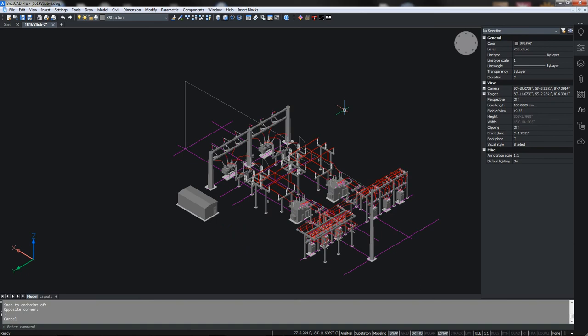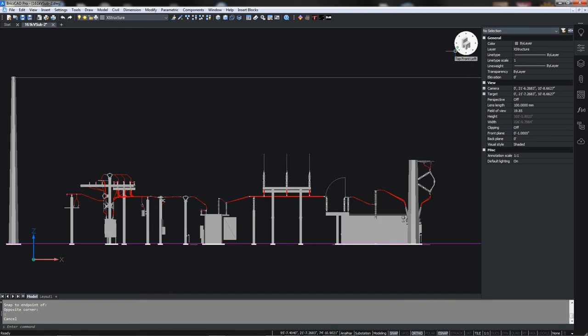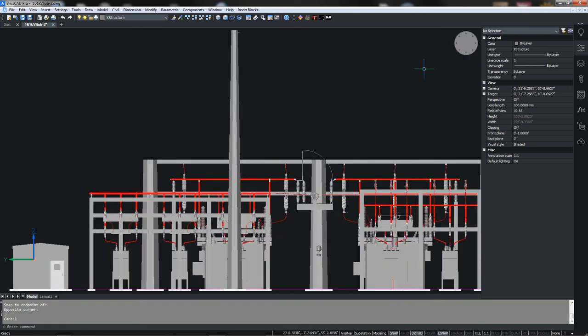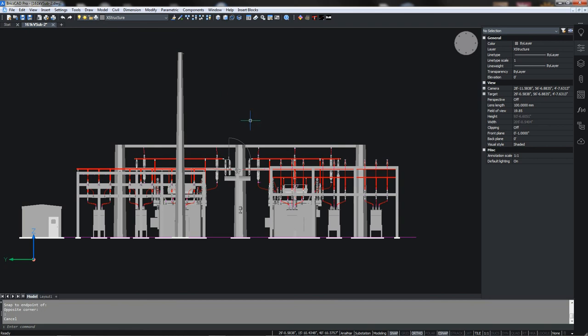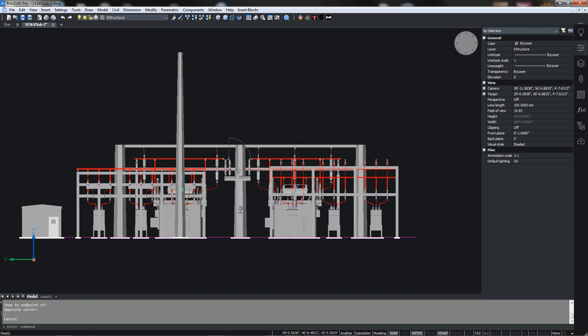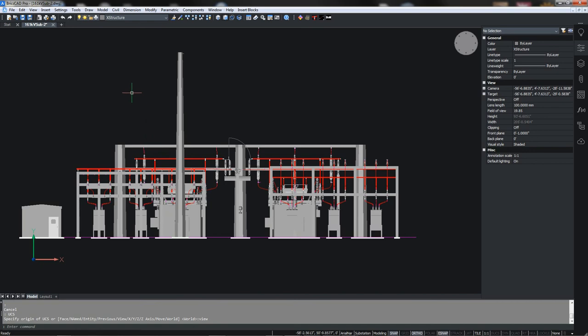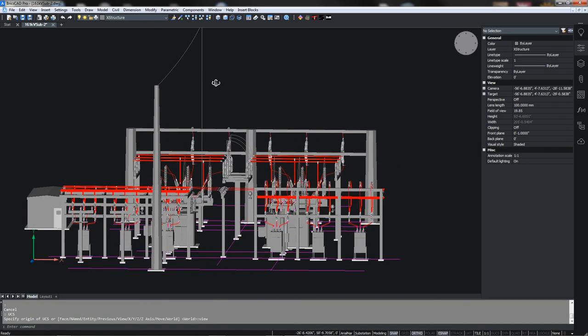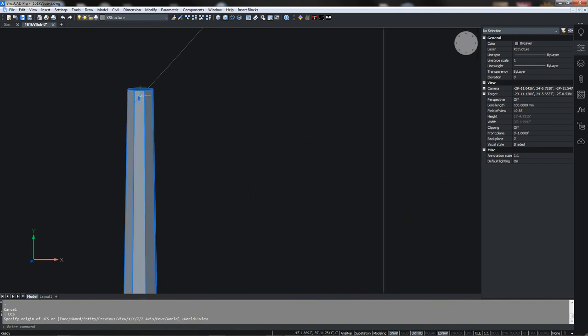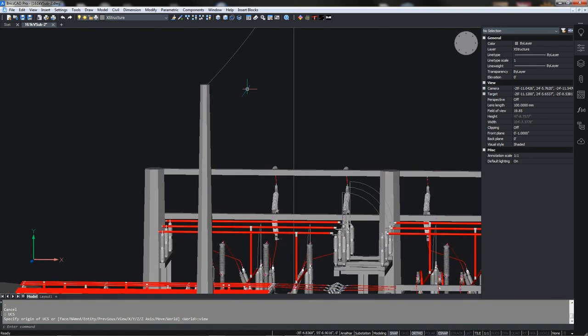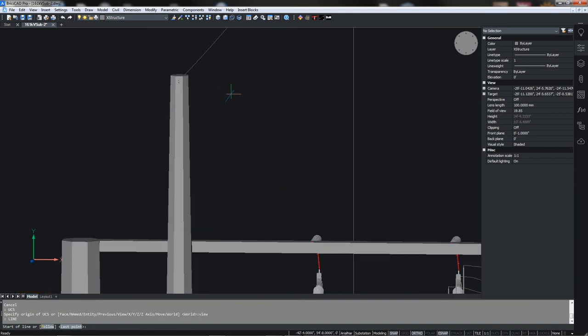Now we want to go to our fixed angle method. First thing I want to do is get the right view. We need to draw our shield lines along here, recognizing that there will be another lightning mast over here and shield wire. On this side we'll have 45 degrees, this side will be 30. In order to draw that line we really need to have our UCS in the XY plane to simplify that construction. We simply use the UCS command and we want it to just be the view that we're looking at, so we use the view option on UCS. Now we need to start with putting in our shield lines. I'm going to move this slightly so I can get to the correct point. We're simply going to draw a line at this point starting here at this node.